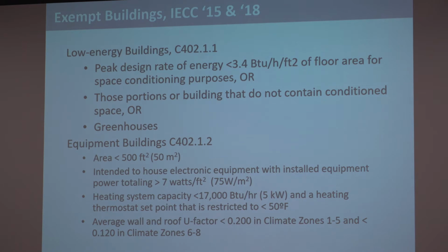IECC has a couple of new exceptions. They're just starting to recognize that not all buildings need to be insulated to quite the level of typical buildings. These are very small exceptions, low energy buildings and equipment buildings, if you've got like an electrical utility house on your site, you'd have to talk to your mechanical engineers and make sure you're under the right power, watts per square foot, or energy use per square foot, and make sure it's under the area, but these buildings wouldn't necessarily need to be following the prescriptive level of insulation. They either don't need it or they need much less insulation than typical buildings.